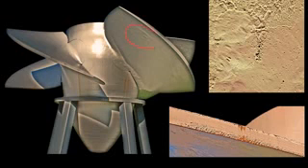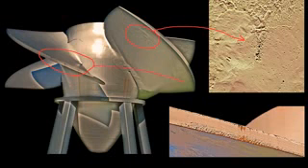On the low-pressure side of the turbine blade in approximately this location, we can see some evidence of the type of surface pitting that is typical of cavitation damage. Another example of cavitation is located in approximately this area of the blade tip of the turbine runner.